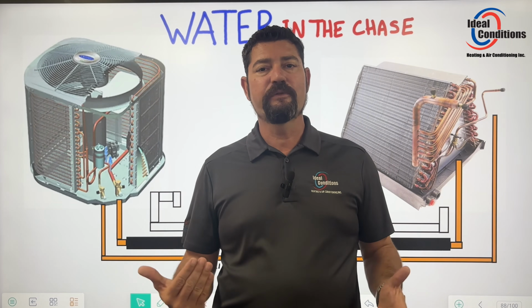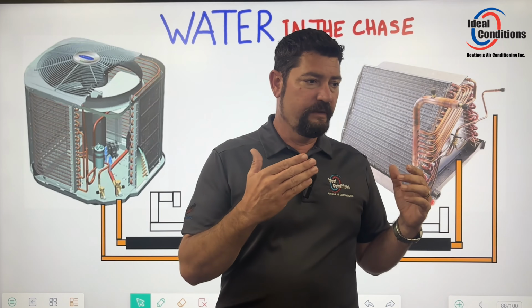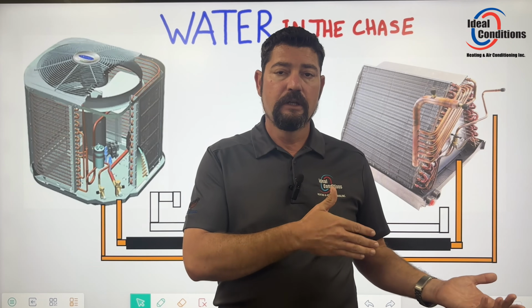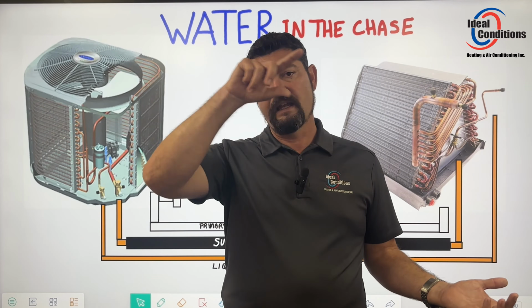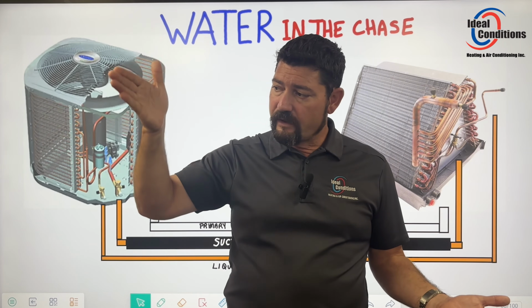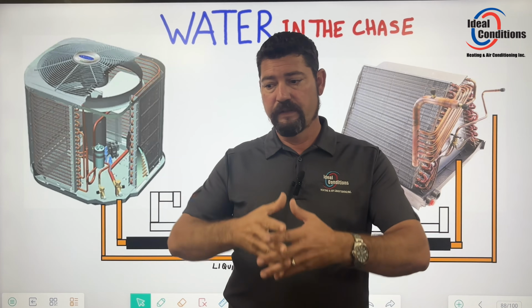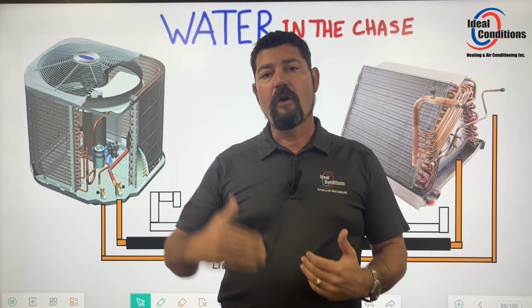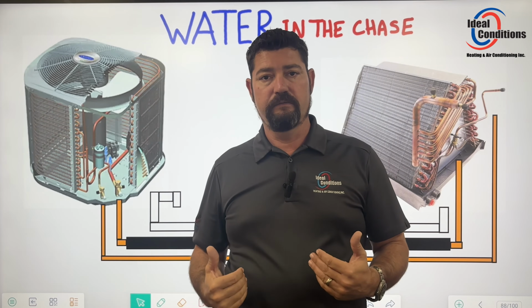Maybe you had a 14-degree superheat at the evaporator coil, but by the time it went across that hot attic, without insulation on that copper pipe, and down the side of the building, it heated up with the heat index and how hot the surrounding ambient air is. All that is adding more superheat to it, right?